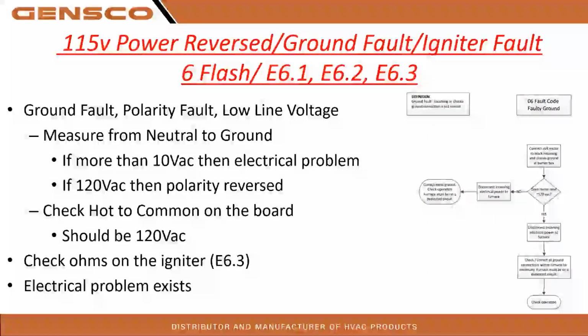So 115 volt power reverse, ground fault, igniter fault. So this would be a 6 flash, or respectively on the shorter furnaces, we're going to get a 6.1, 6.2, 6.3. Okay. So obviously I just stole one of the fault codes out for the faulty ground. But there are several of these flow charts in the service facts for those model furnaces. So hopefully you guys have literature racks or something like that, and you're keeping it with the homeowner, or the homeowner's got it somewhere where you can access it and troubleshoot.